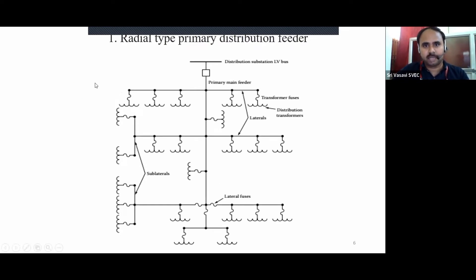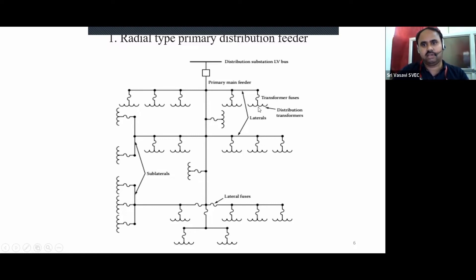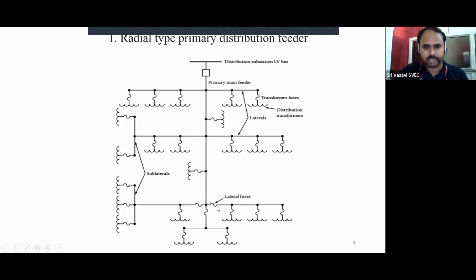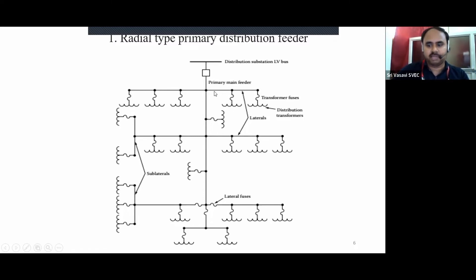The first type is the radial type primary distribution feeder. It consists of a distribution substation low voltage bus, a feeder breaker, a primary main feeder, transformer fuses connected to distribution transformers, and from the secondary winding of distribution transformers, consumers are connected through service mains. The laterals are further subclassified into sub-laterals, with lateral fuses. This is the design of the radial type primary distribution feeder.